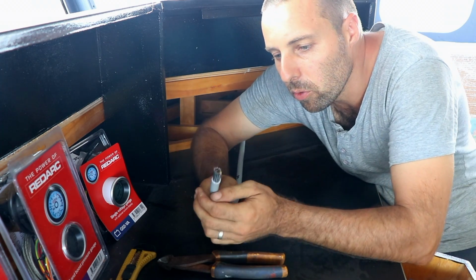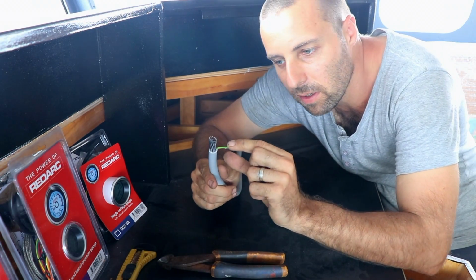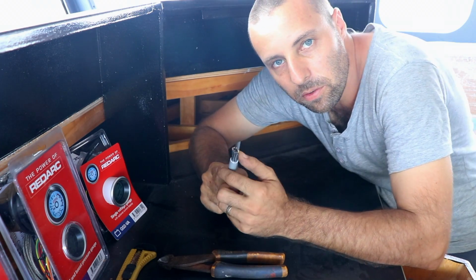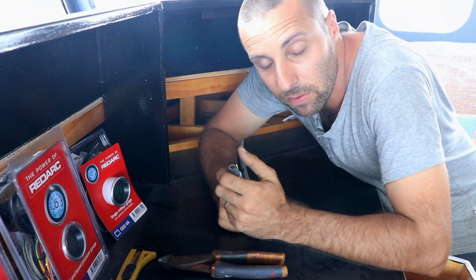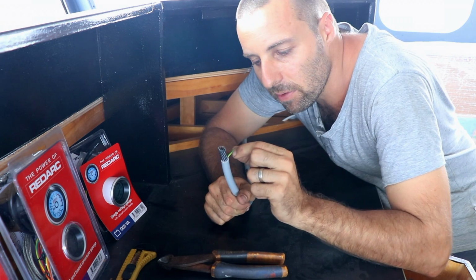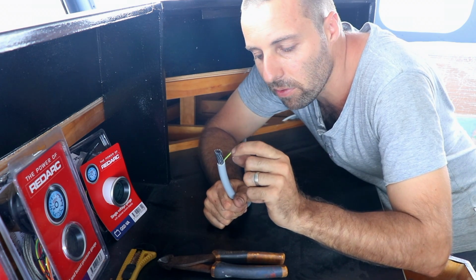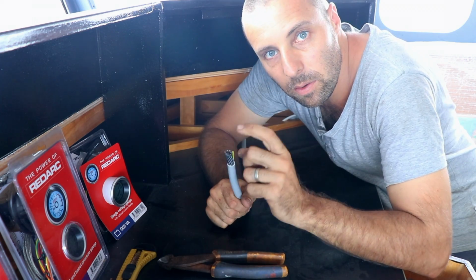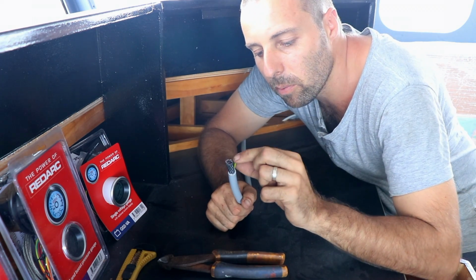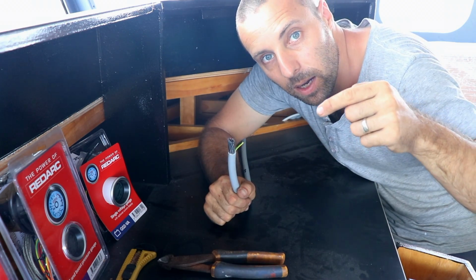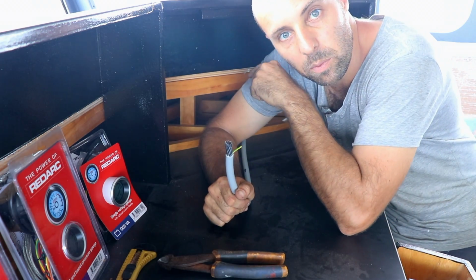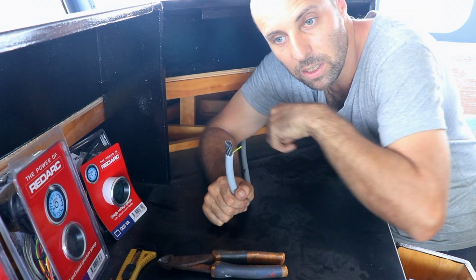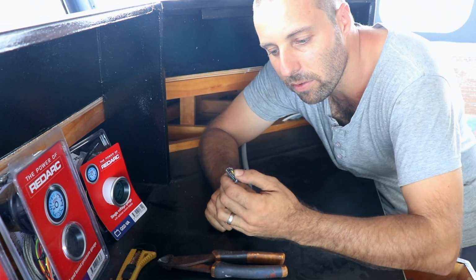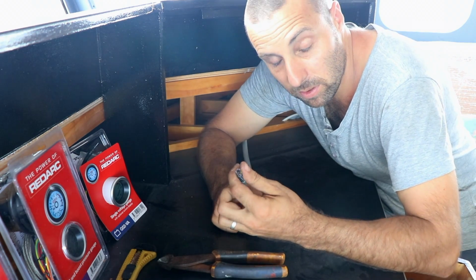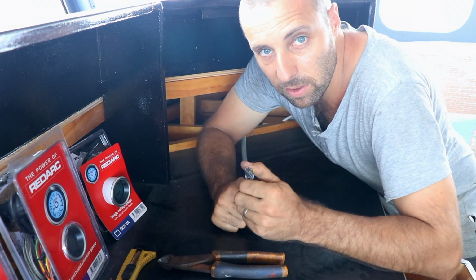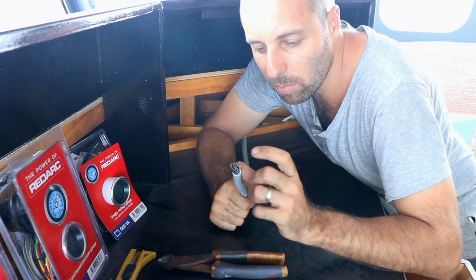These big thick grey cables are 18 conductors each, so 17 conductors plus a single earth. We won't be using the single earth in any of these cables, we'll have a separate earth. We're actually going to use these as a tester for continuity later on, so if we ever need to figure out if we've got a break in any of the cables, we'll keep one spare so we can run current up it. At the other end we'll join it to whichever one we're checking, and run essentially a circuit all the way around. So we're keeping this one as a spare for later - if we desperately need it we can use it, but most of the time we won't have anywhere near that level of stress. We're going to have plenty of redundancy.